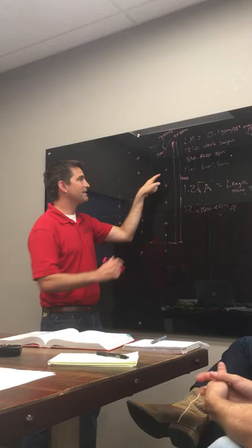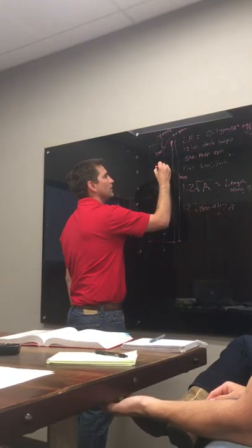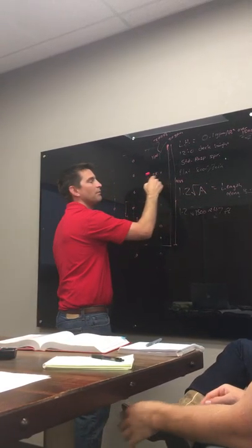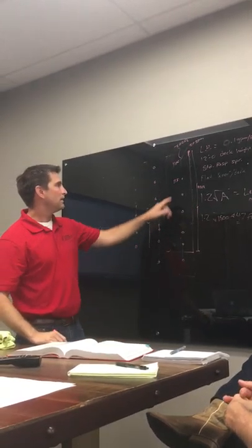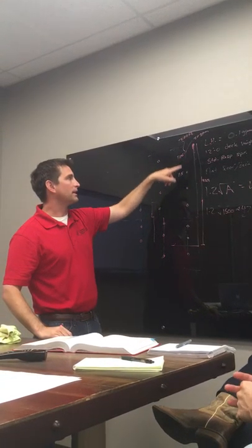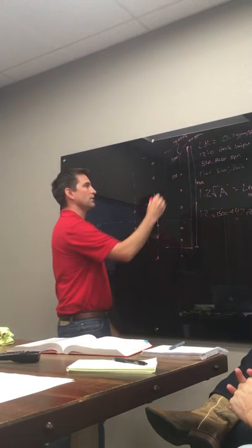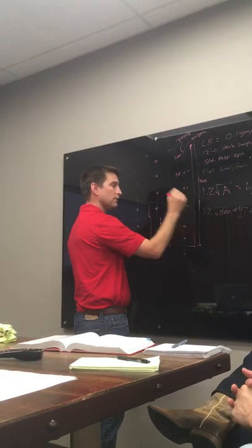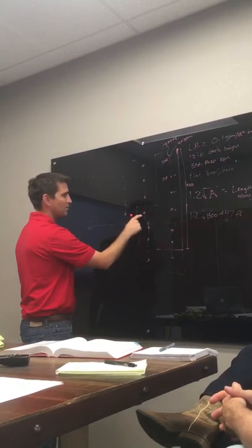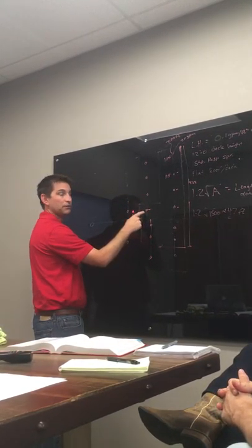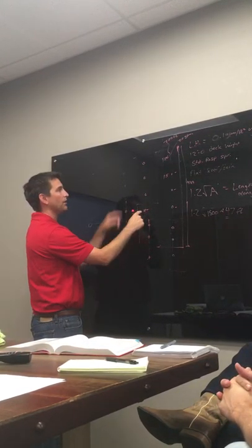So now if it's higher, say 11.5 PSI at that point, same sprinkler, is that going to flow more or less than 20 gallons a minute? It's going to flow more. Right, I have to flow more, even more. And so when I get to this point, this head is actually going to overflow, as we call it, more than this head.